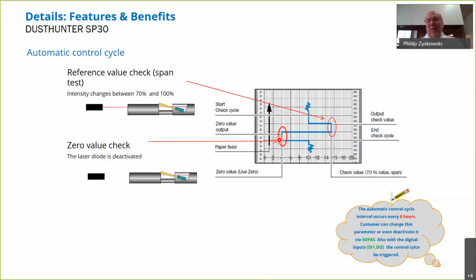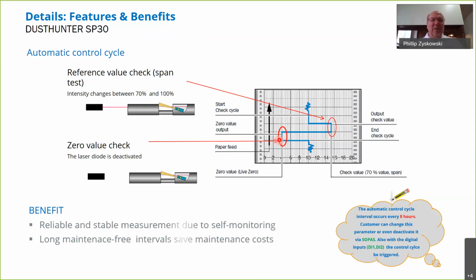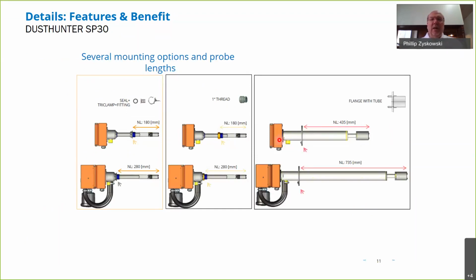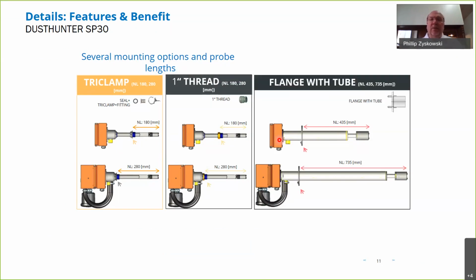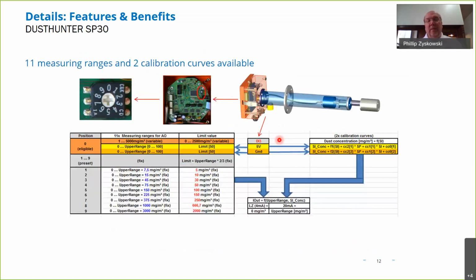So this happens every 8 hours. You can change it. We'll get into SOPAS in a minute to show you how you can do that in SOPAS, our software, but it's user selectable. So it's a stable measurement, maintenance-free intervals, and very low maintenance cost. Just briefly, I mentioned there were 2 basic different models. So for the smaller duct work and smaller path lengths, we've got threaded tri-clamp, and we can also go with a flange that's welded onto the ductwork and with a larger length. So no matter what size your duct, we've got the right length available.